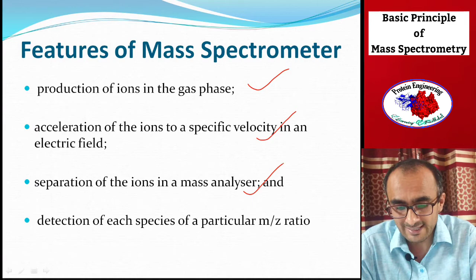The first step in a mass spectrometer is ionization of the sample. A sample is ionized by different methods, and when a sample is ionized, the ion may be unstable, so it can give rise to daughter ions also. Then this beam of ions is focused and accelerated using a high voltage, and the accelerated ions are allowed to pass through a magnetic field. As per electromagnetism, when accelerated ions go through a magnetic field, their trajectory is not a straight line. In fact, it is curved into a circle, so their path is deviated. This deflection of ions under the magnetic field is measured in a mass spectrometer and used to calculate m/z of specific ions in the sample.